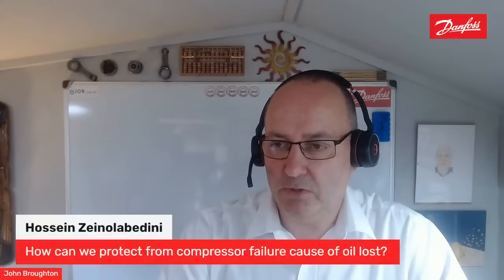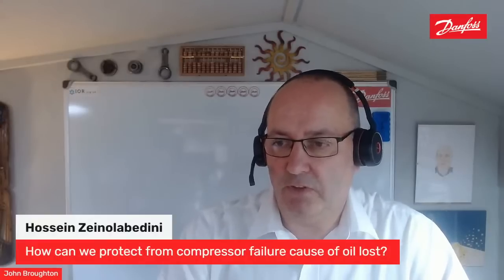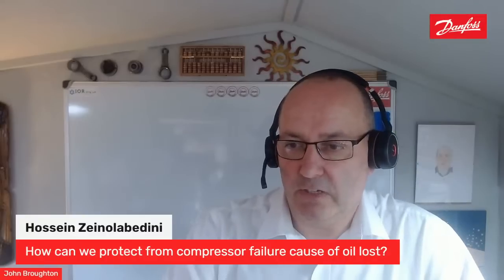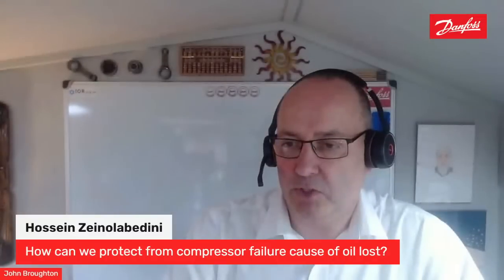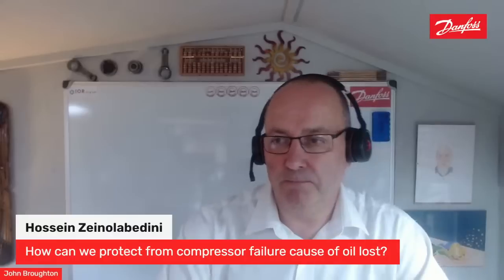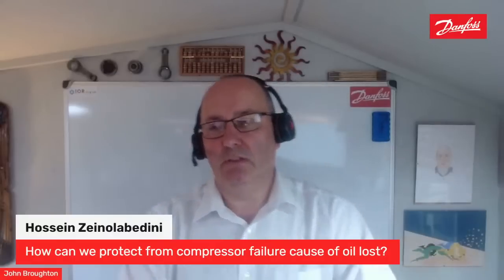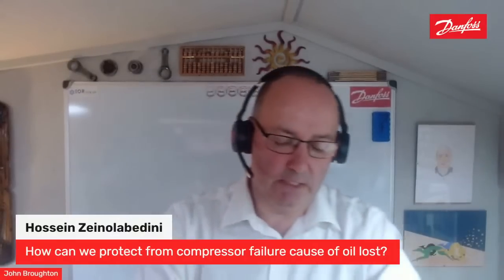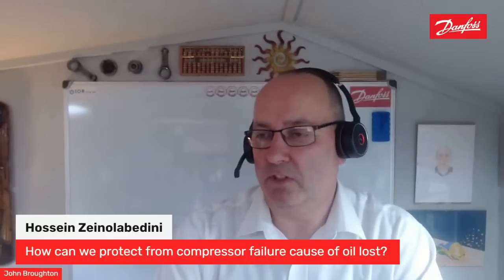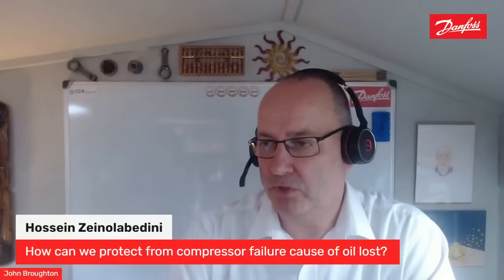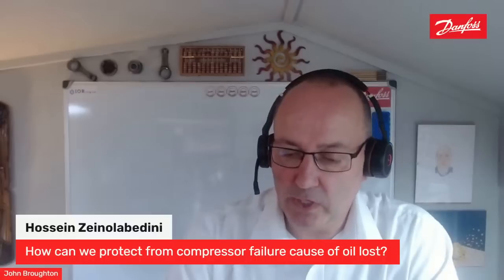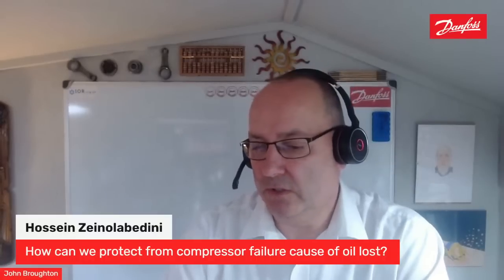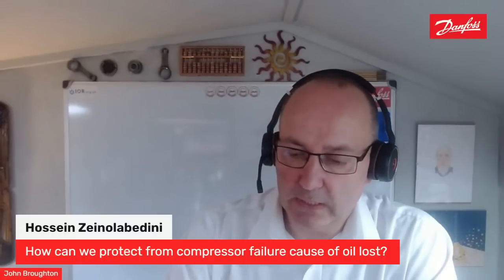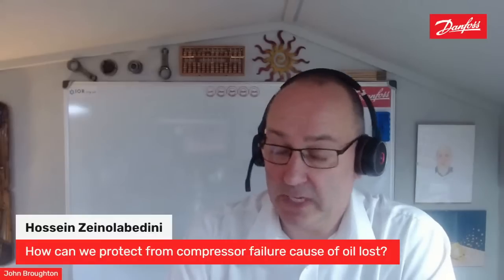A question from Hosin: how can we protect from compressor failure because of oil loss? Do Danfoss compressors have internal temperature protection for this reason? Good question. We make hermetic compressors, so hermetic scroll compressors and hermetic piston machines, and we don't have an oil pump on those machines.